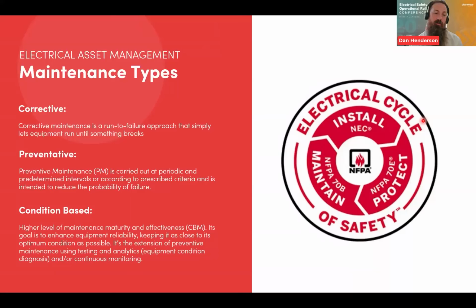What we'll be doing in a minute is putting a poll on just to see where everyone on the call fits, whether you have corrective, preventive, or condition-based as your approach. What I will say is I would probably expect that we'll have 0 in corrective, because we do preventative maintenance. We've got computerized maintenance management systems, we've got PM set up for everything, and typically that is what I would expect. And I would think the professionals we've got on would be the case. But often, especially from an operational side, you'll have your PM set up, and then operations gets in the way.